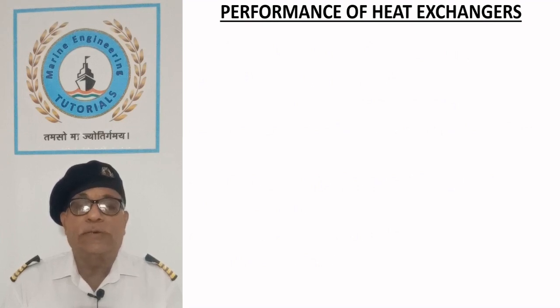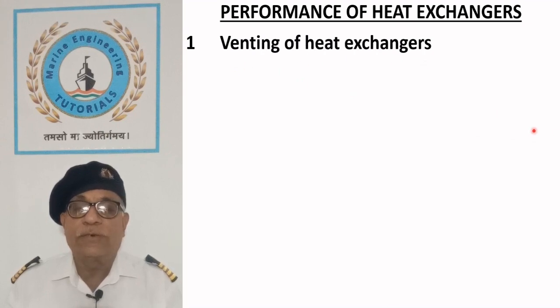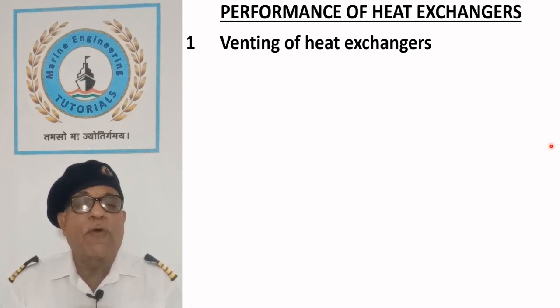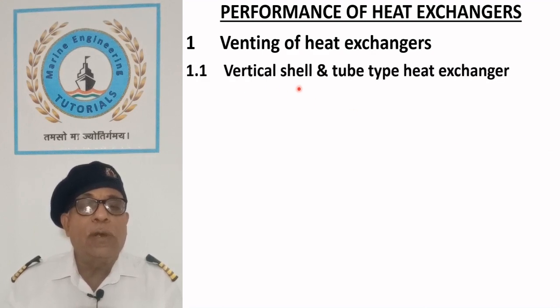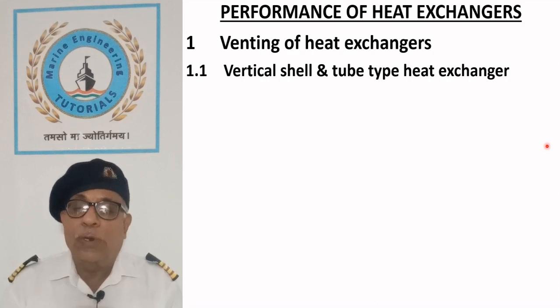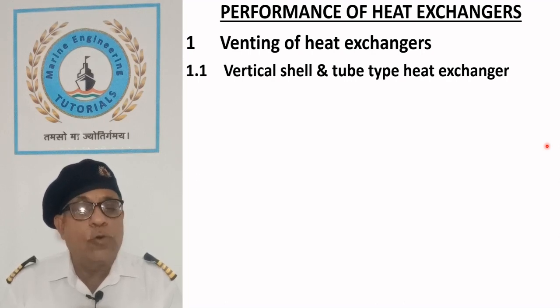Performance of heat exchangers. Performance of a heat exchanger is judged by the outlet temperature, whether it is able to maintain the desired temperature or not. Venting of heat exchangers. Venting of a heat exchanger is most essential for its performance. Vertical shell and tube type heat exchanger. Vertical mounting of single pass coolers will ensure automatic venting. Although this arrangement is good, but it is rarely seen in practice on the ships.